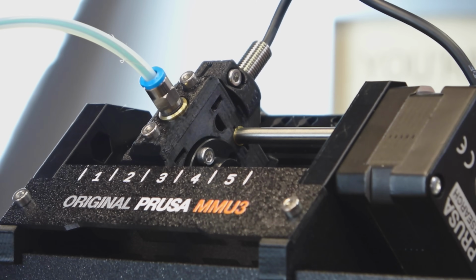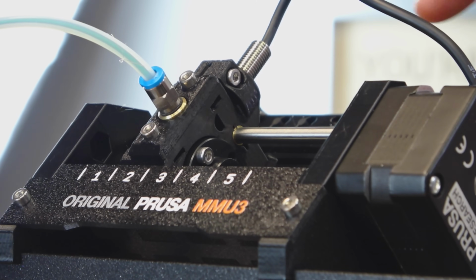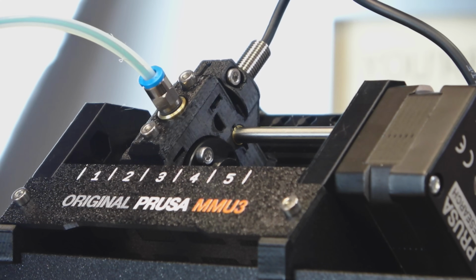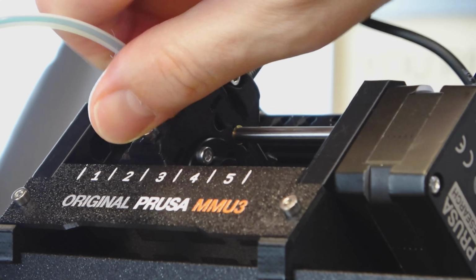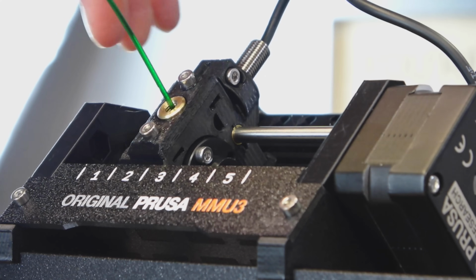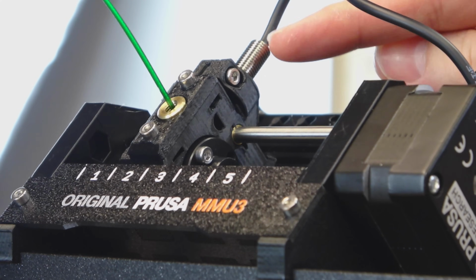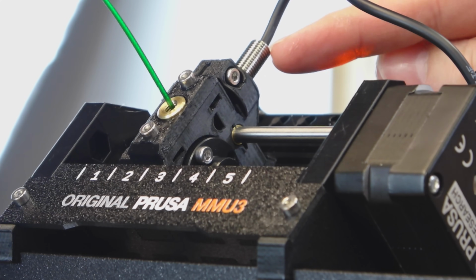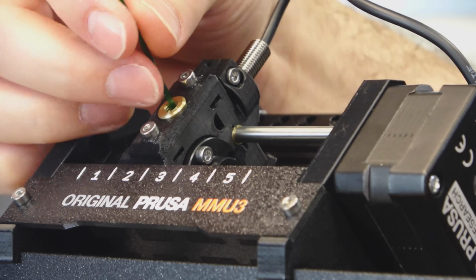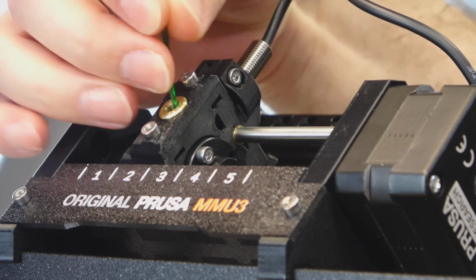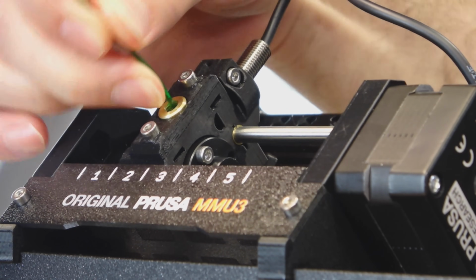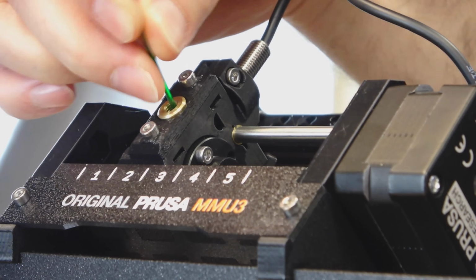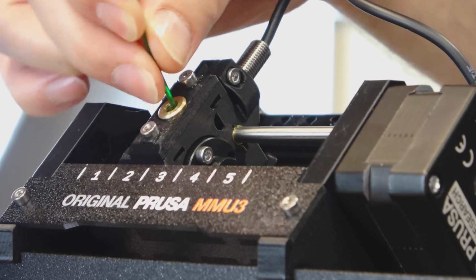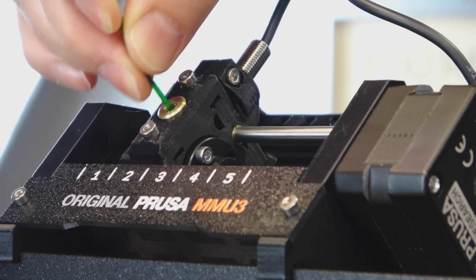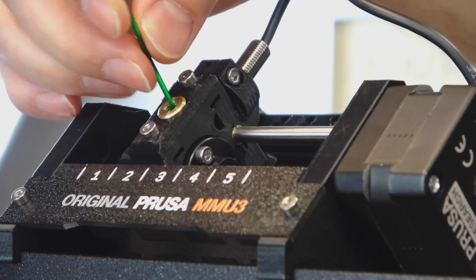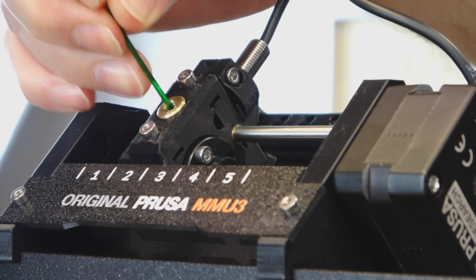Up here at the selector, the screen did show us that the Finda was triggered, but what I like to do is pull the coupler from this side and take a look at the LED here. Remember we discussed there is a light on the top of these sensors. I'll move the filament a bit just to make sure that it's not triggering that Finda probe. The light isn't coming on, meaning that it's not getting a solid trigger on that filament.